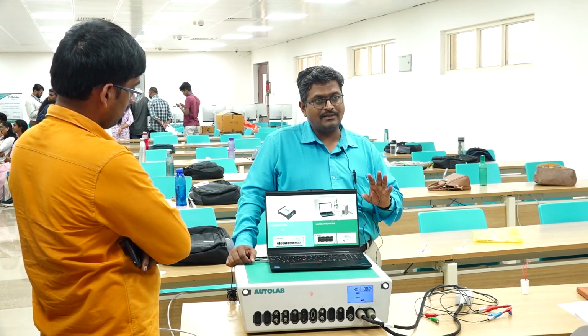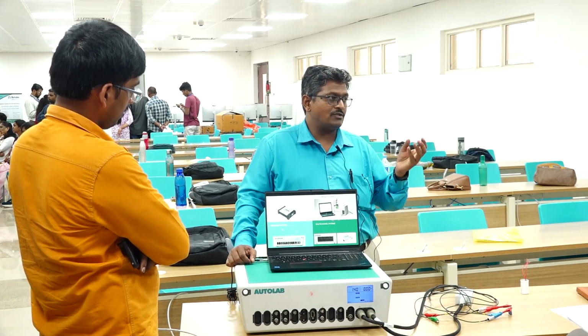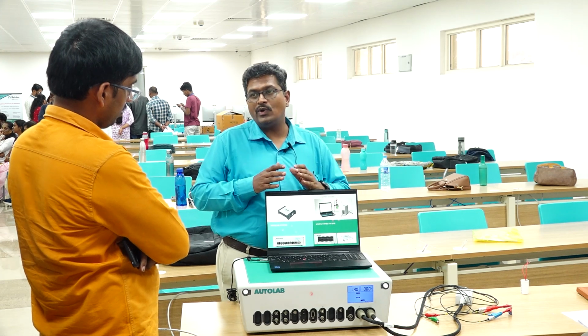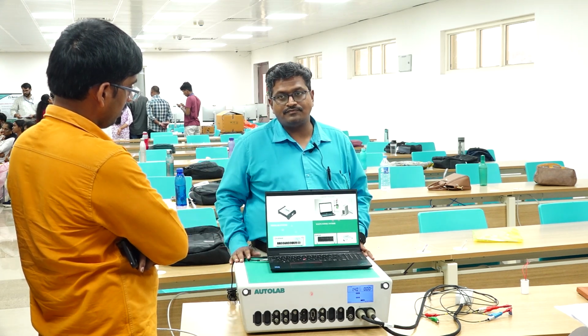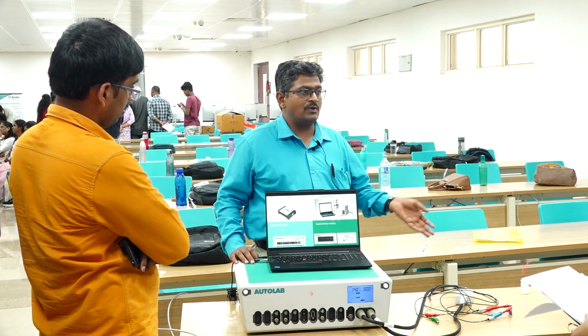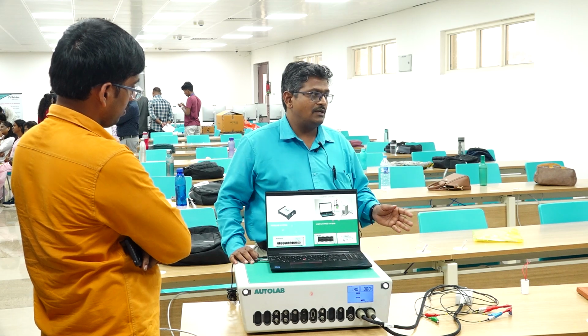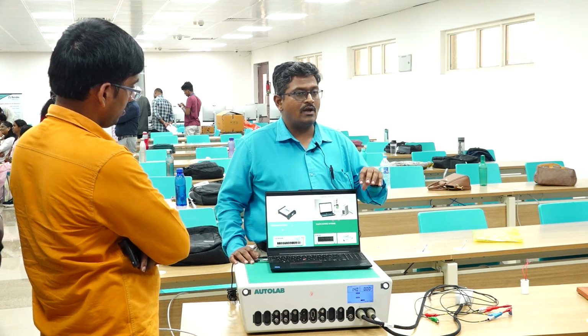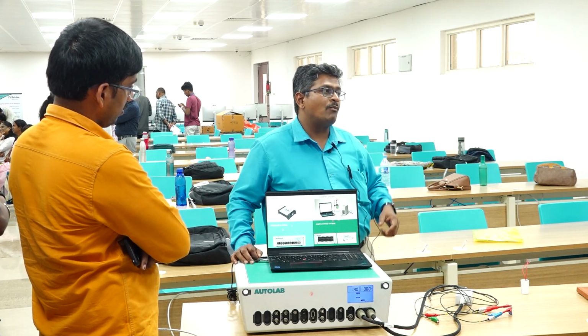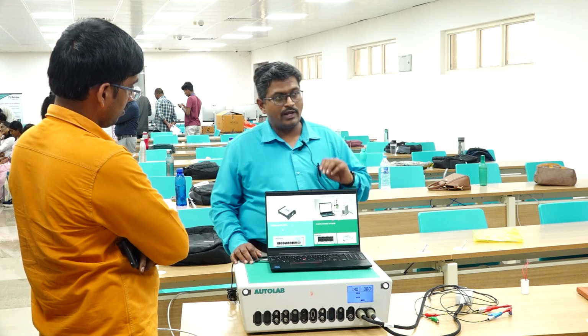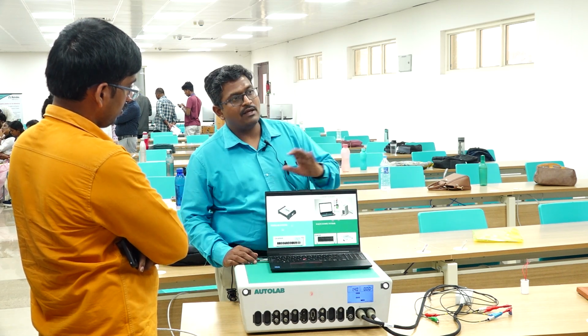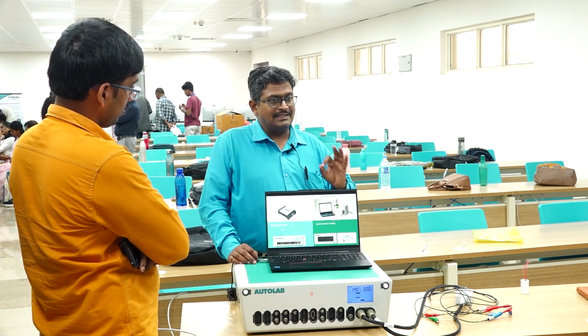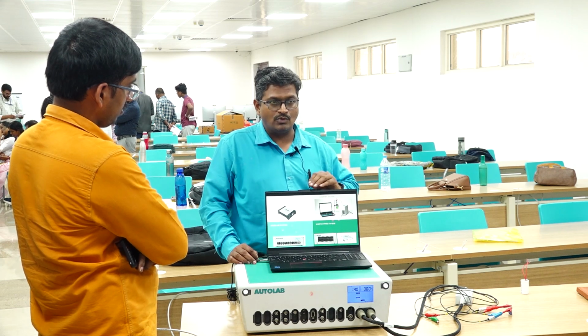So the compliance voltage should always be higher, so that you can do your experiment without any ohmic drop. Whether you are working in aqueous or non-aqueous, any kind of solvent, to avoid this IR drop your instrument should have a little higher compliance. So, choose your equipment accordingly. Apart from many other parameters, these 3 are the major parameters to start with.